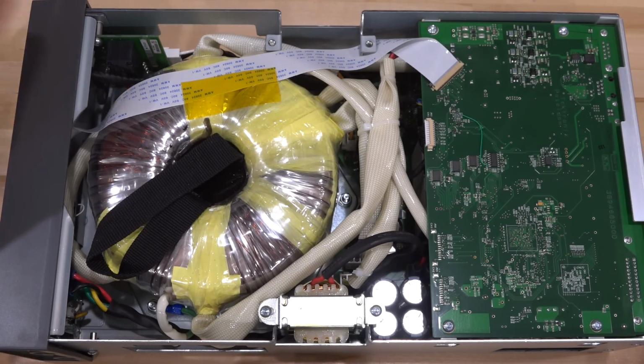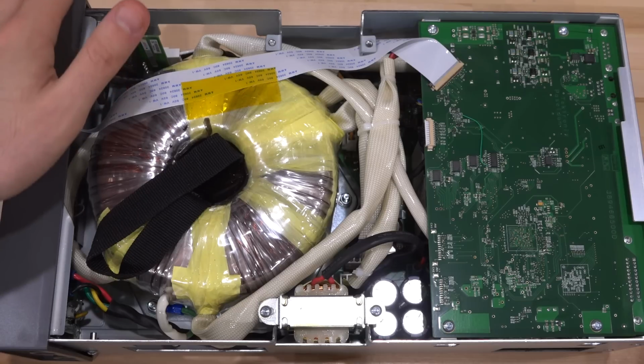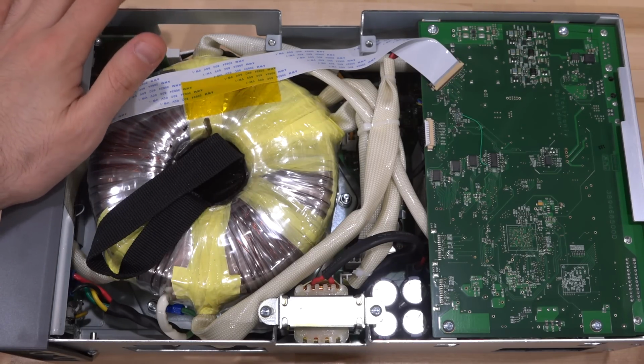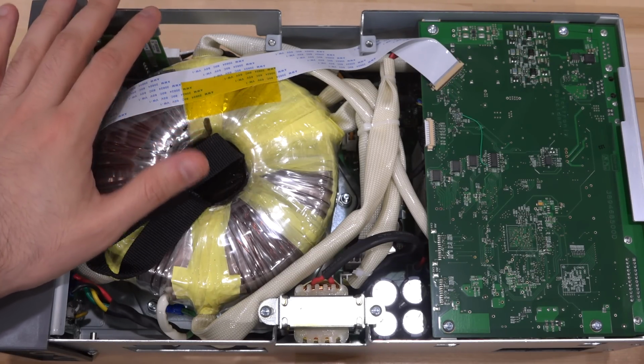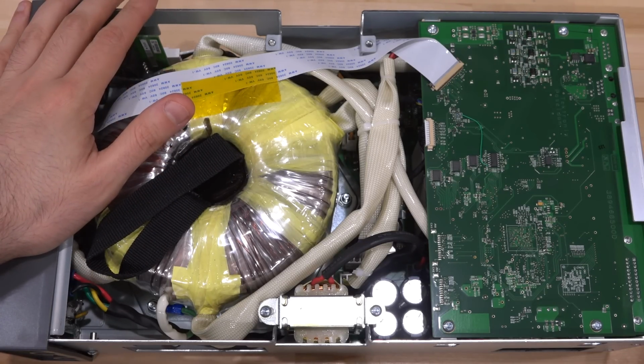Now, the front panel is a computer, a fully self-contained computer, which is where all the GUI runs and everything else. This is again a common architecture. Now this computer is not as sophisticated as the one that's on the source meters with a nice touch screen and so on, but it is running the same code base because it does have the same GUI elements and everything, which is nice to see in this power supply too.